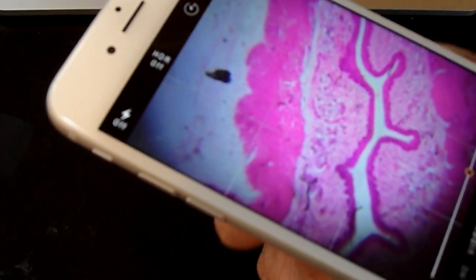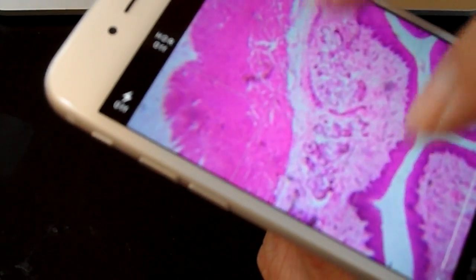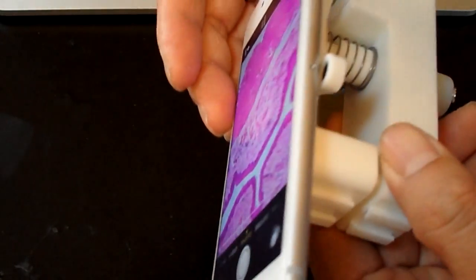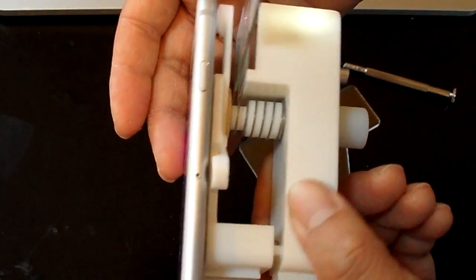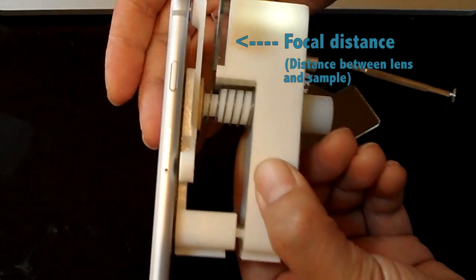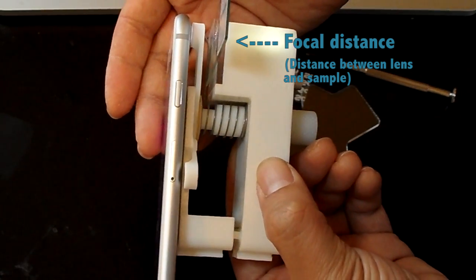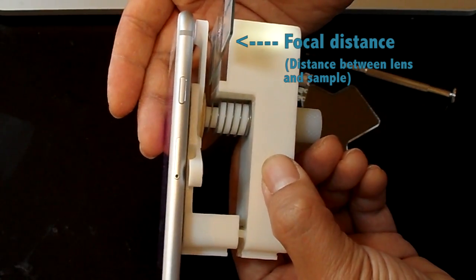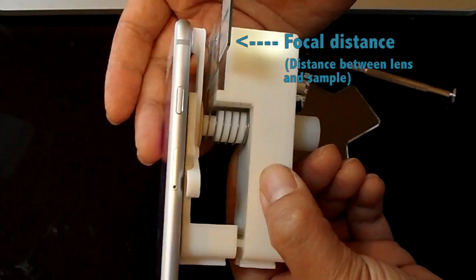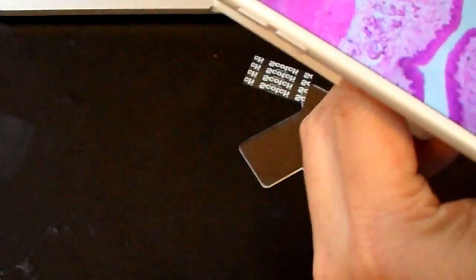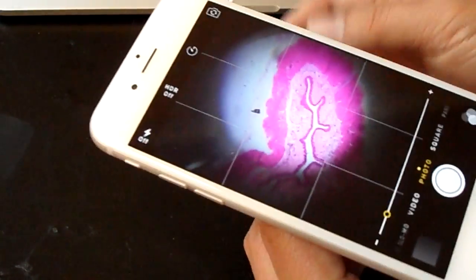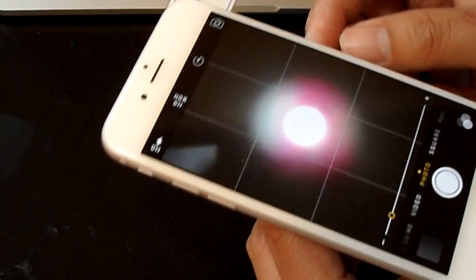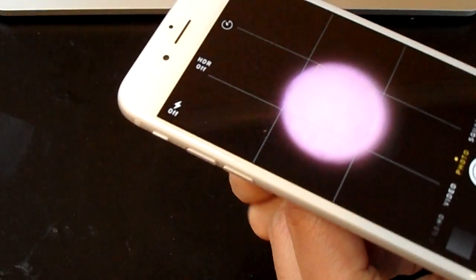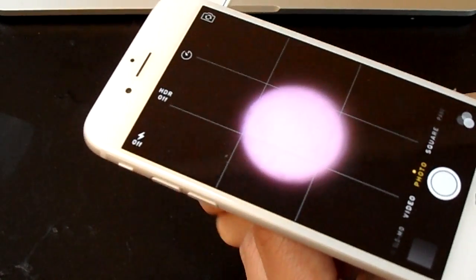Okay, so what I just did was get it off the highest power magnification and get it down to the 30x lens, and it just so happened to already be pretty much in focus. But one of the main things I want to show you with this is what's the correct distance between the lens and whatever you're looking at. This is the focal distance, and this is what you should be shooting for when you're trying to focus the microscope. And for the 50x lens, it's pretty much the same distance, it's just a little bit closer.